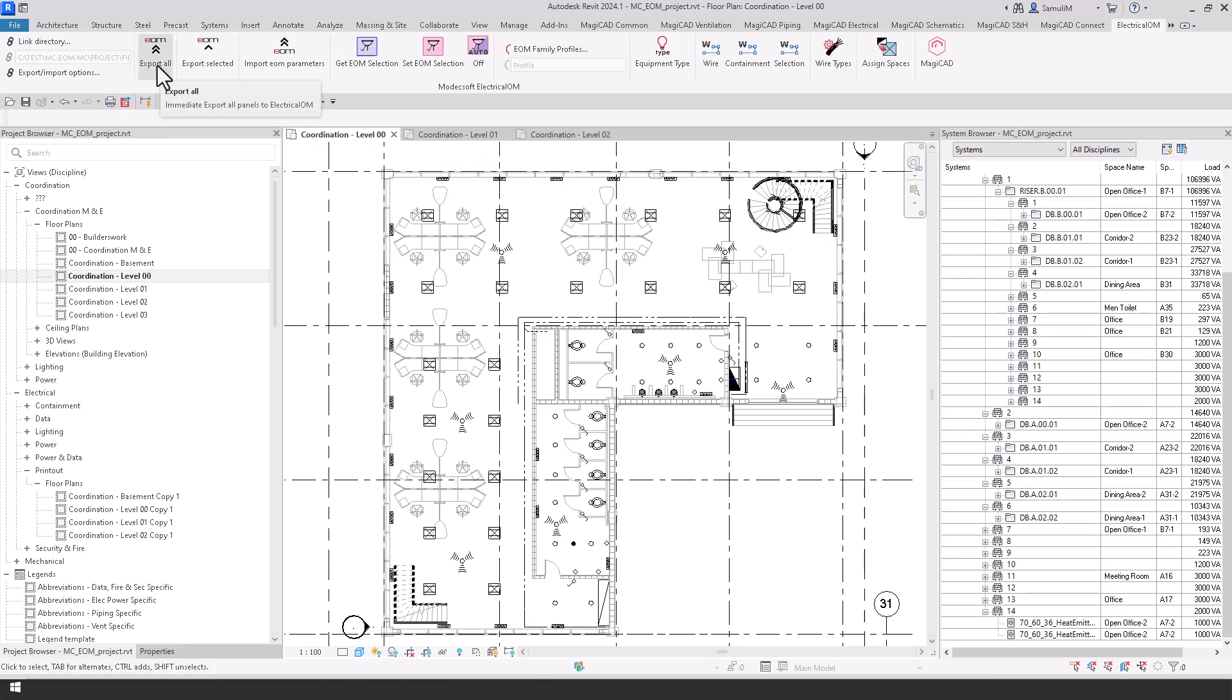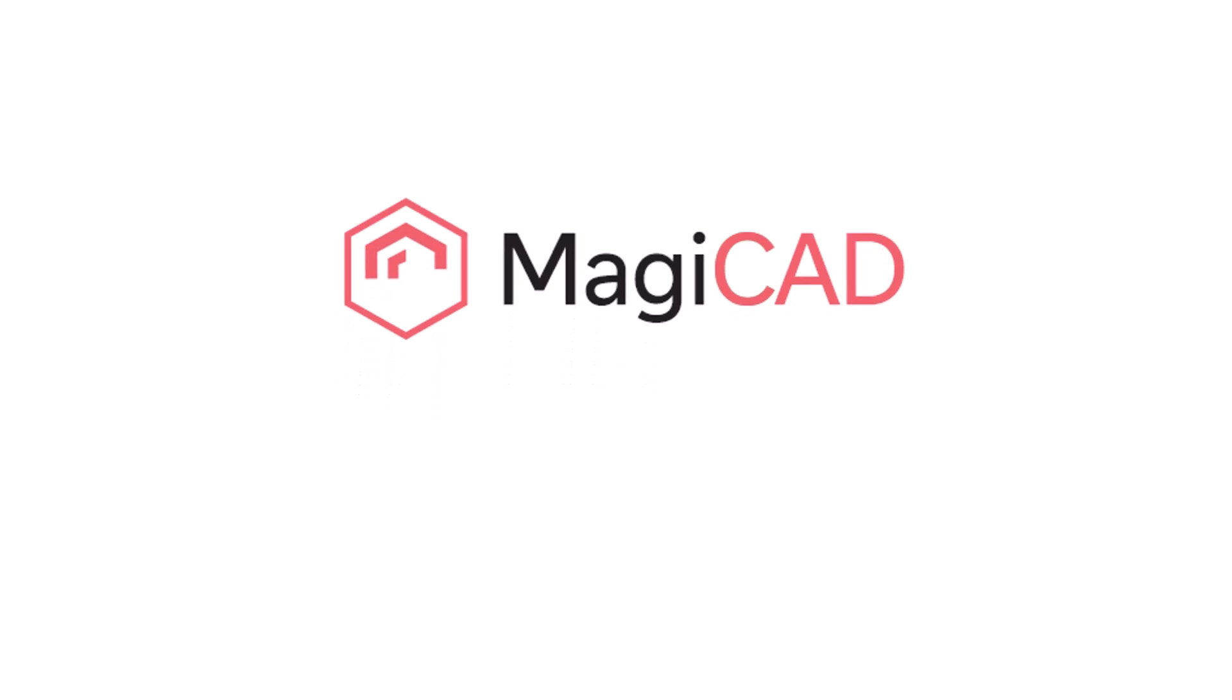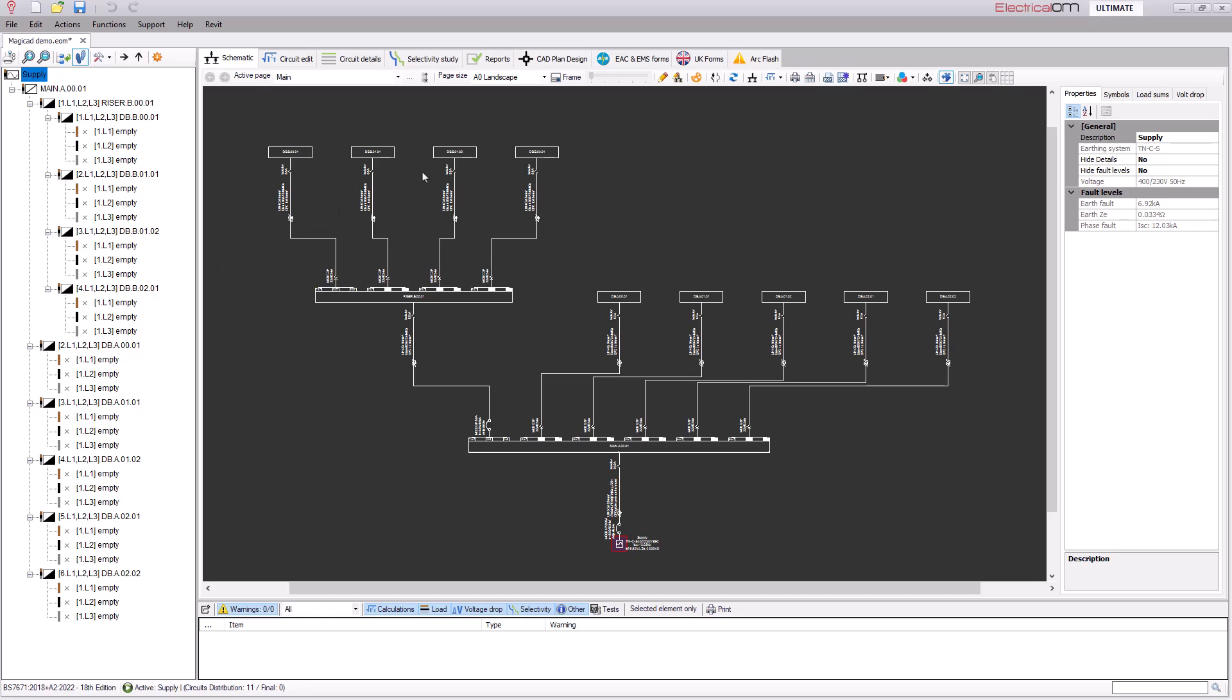But if I go back to ElectricalOM now and the MagiCAD tab we can now move this model stage to full design and then with the check boxes we can check which parameters that we want to export back to ElectricalOM so that we can go through the full stage design on here. And these are just some of the parameters that are going to be exported. So now if I again like previously go to export all on the ElectricalOM tab and I'll get a successful warning. And then from here we're going to go back into the ElectricalOM software.